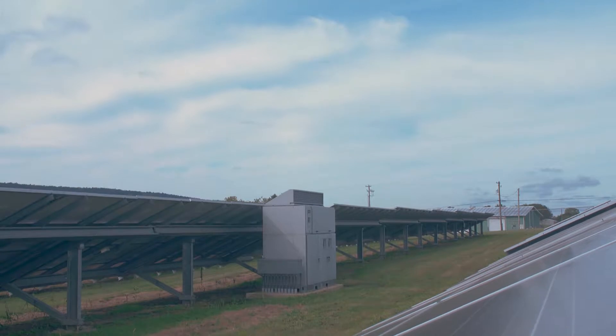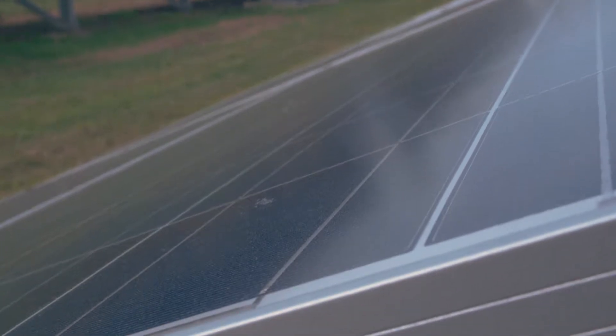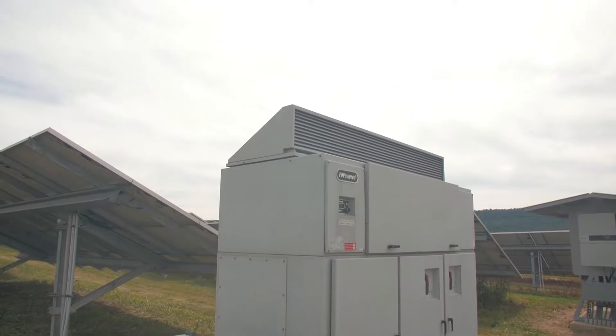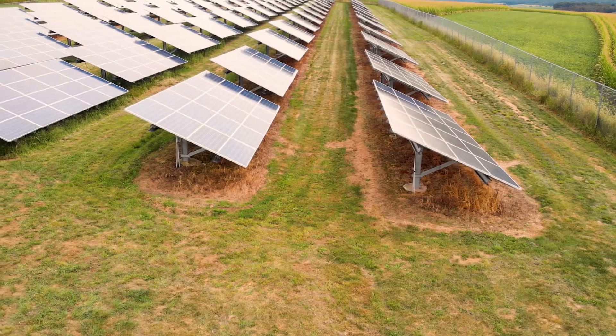The biggest issues with having the old inverters were a combination of a couple different things. Number one, the age. We were getting on the 10- to 15-year mark, which everybody knows that's the point where you start getting more failures. And the customer already had issues particularly with this one inverter, so they decided to upgrade.